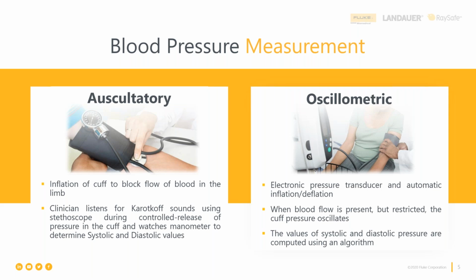So you don't want to try and compare one measurement against a different measurement in any respect, whether it's on an opposite limb but at the same time, or whether it's making the measurement with the oscillometric automated technology and then making a completely different measurement even on the same limb and auscultating it. None of those are apples to apples comparisons at all, and they will never produce the same result. So just keep that in mind.